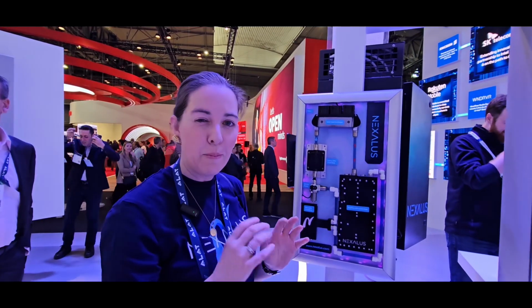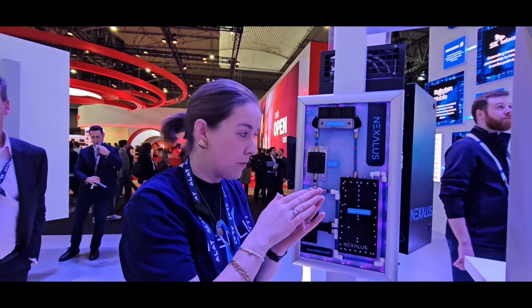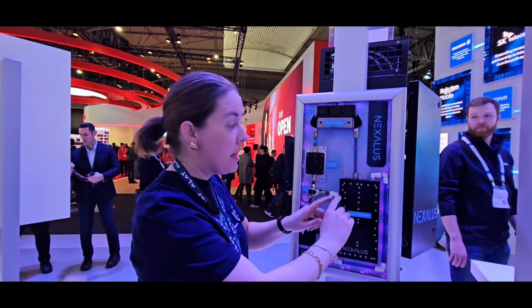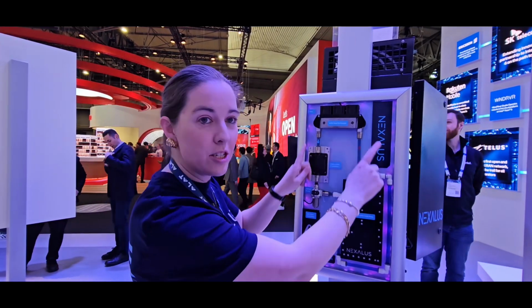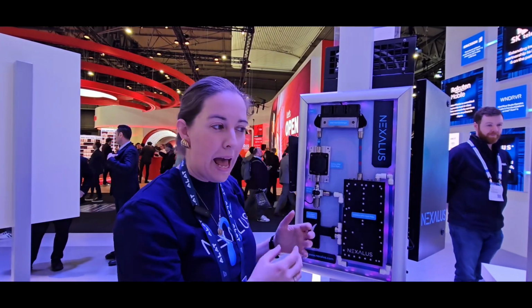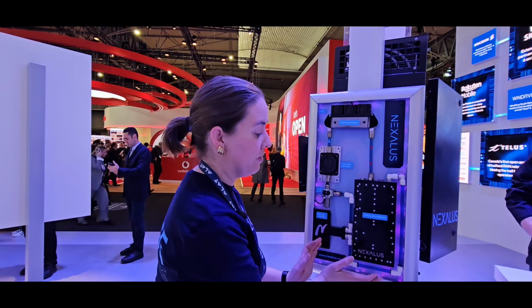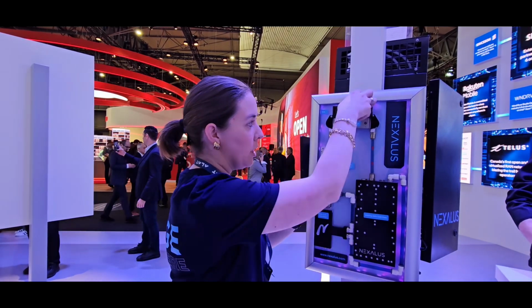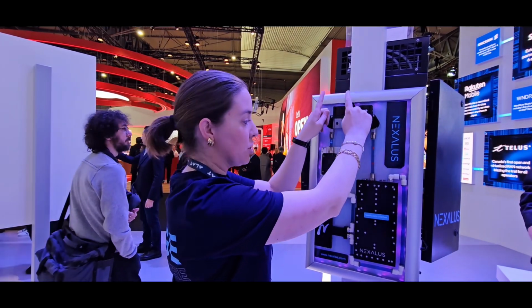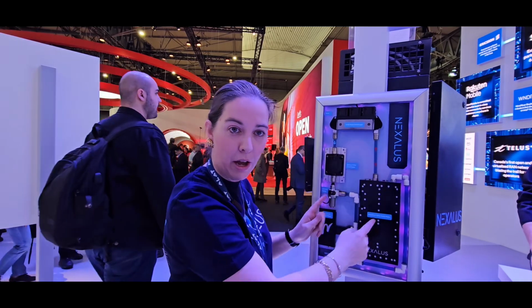The other thing that we do is we're sealed servers. We're one of the only companies that actually seal the server. Before we do so, a small amount of air is trapped within the system, and we use that air then, circulated on a continuous basis, to cool any of the lower powered components, things like your PSU, your DIMMs. Again, the air would be driven up, pulled through your heat exchanger, and recirculated back around through the system.